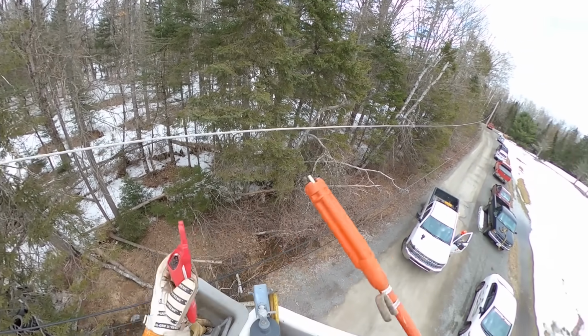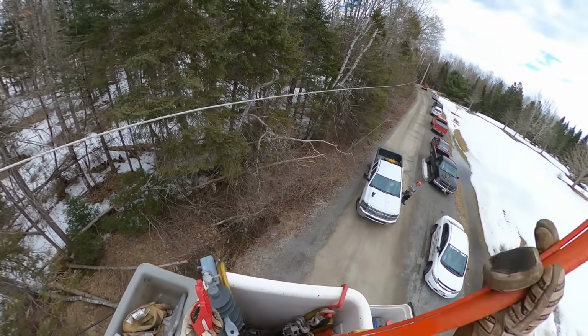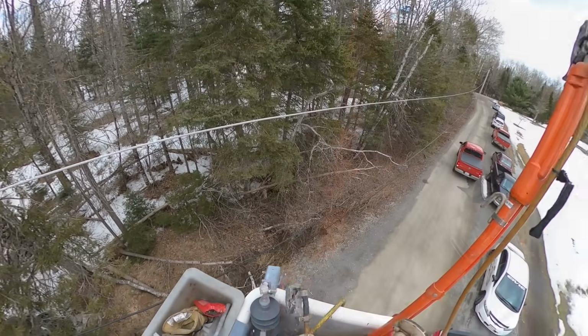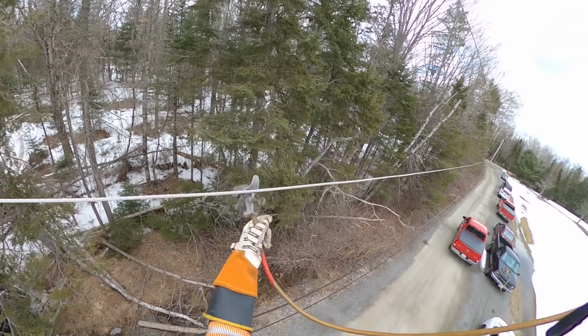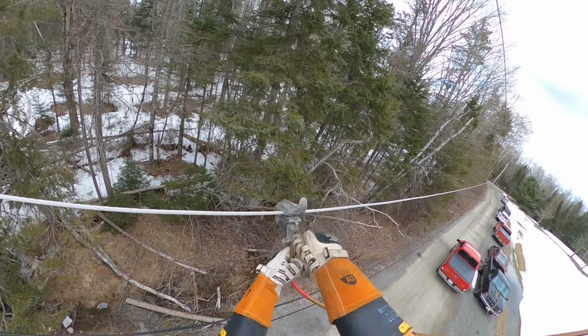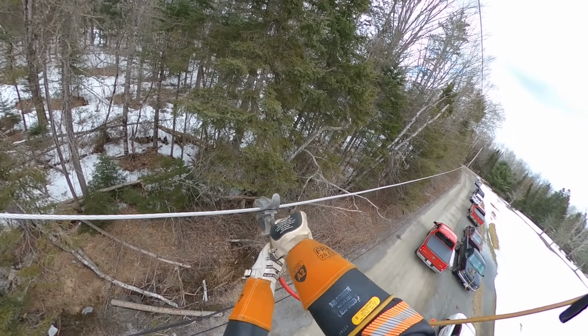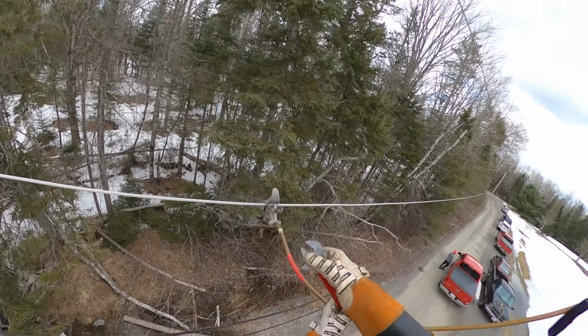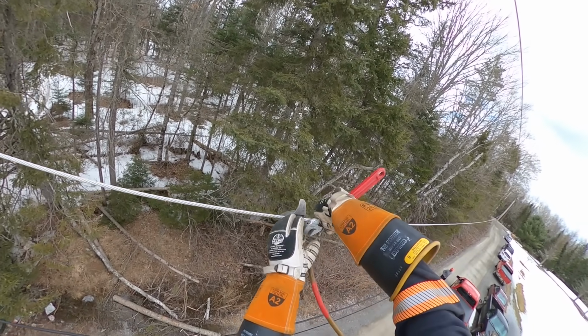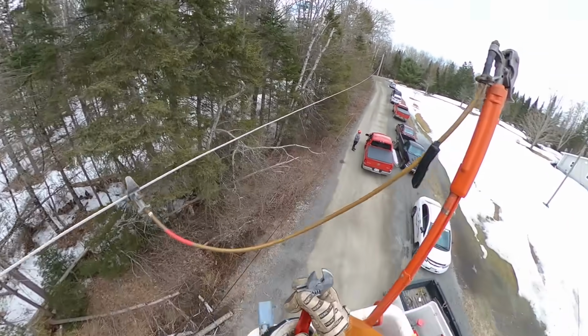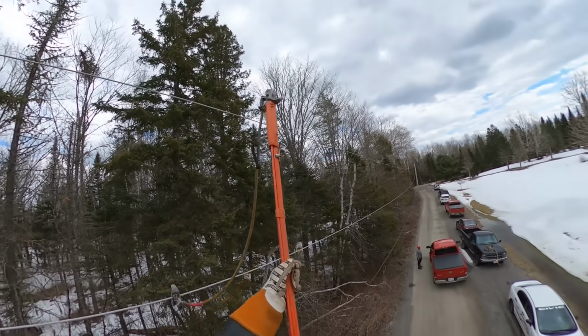Oftentimes people inquire about testing your equipment on something live to verify it's working. If there's some live conductors close by, perfect. If not, the proximity detectors do run through a self-test function. So there was no voltage. Our next step is to install our ground. This is going to be our trip ground, which will also ultimately function as a bond.